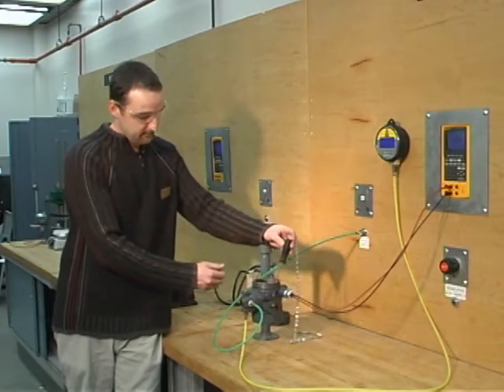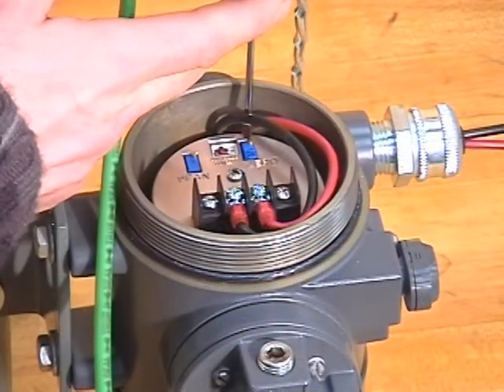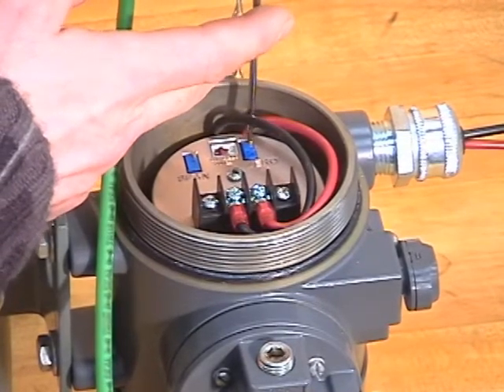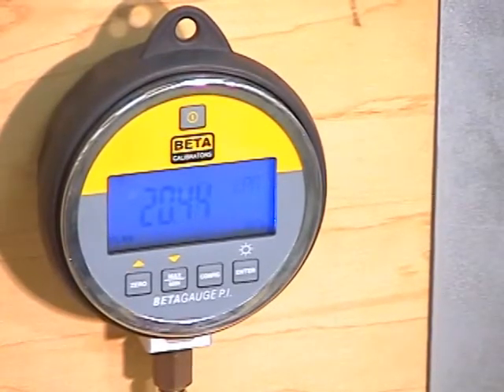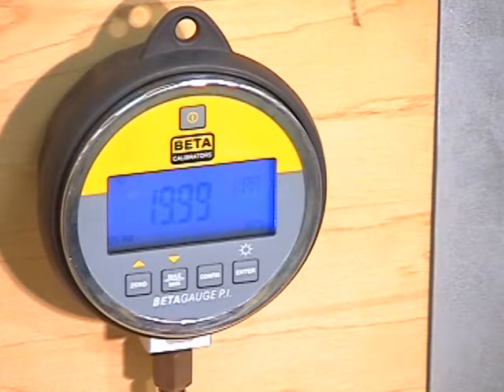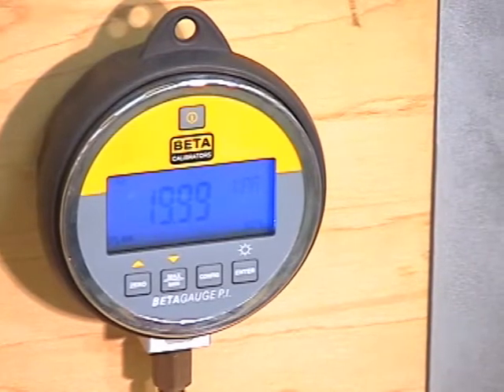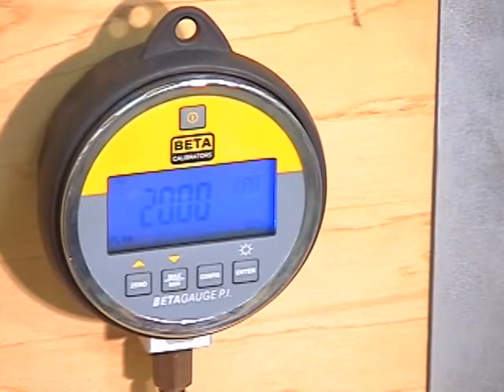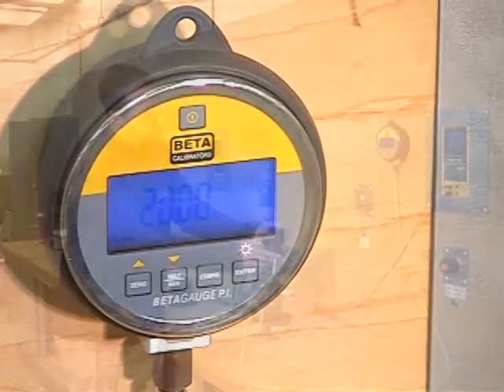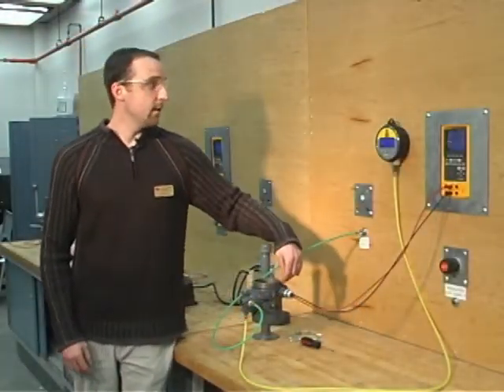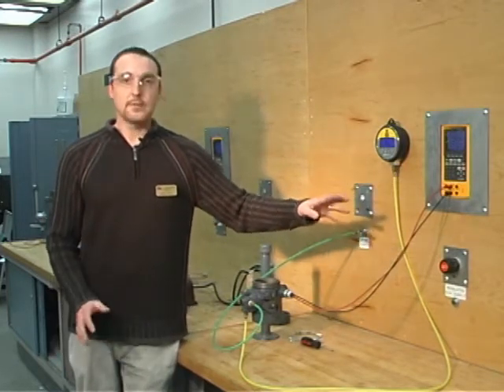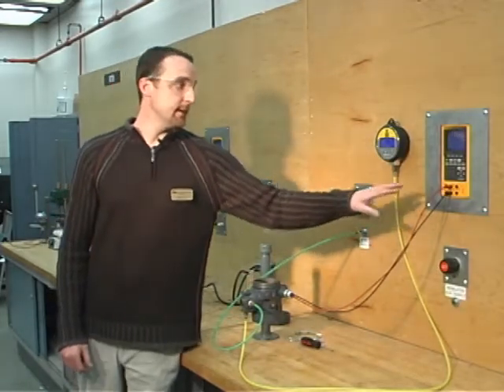So if I make a slight adjustment with our zero screw and slowly decrease the output pressure. It's very important to be as close or as accurate as possible. There we are, 4 milliamps, 20.02 kilopascals. It's okay to be plus or minus 0.05 kilopascals for our output scale.